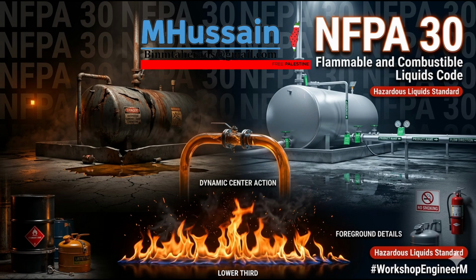Class IIIA is 140 up to 200 degrees. And Class IIIB catches everything 200 degrees and above. Think heavy lubricating oils, motor oils, hydraulic fluids. So a Class IIIB liquid needs a ton of thermal energy to off-gas enough to ignite. I feel like you could almost drop a lit match into a bucket of some IIIB liquids at room temp and it would just put the match out. You likely could, actually. Really? Yeah, but that high flash point often lulls people into a false sense of security.